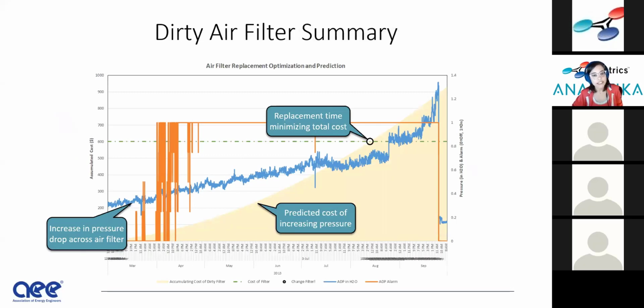Here's a dirty air filter example. This is one of my favorite examples that I've spent a lot of time with. Dirty air filters, I think, are a great example to talk about the differences between preventative maintenance and predictive maintenance. This, first to show the plot, it's another time series chart. In orange is our differential pressure alarm. This is an actual alarm point from the BAS. The blue is the differential pressure across the air filter. And I'll talk about this yellow, but this is essentially the accumulated cost of not replacing that filter.